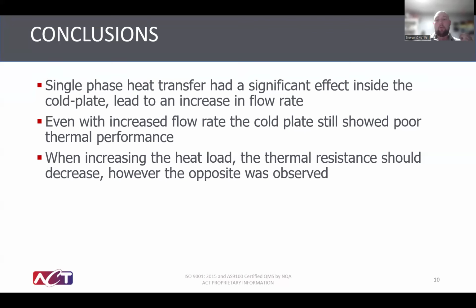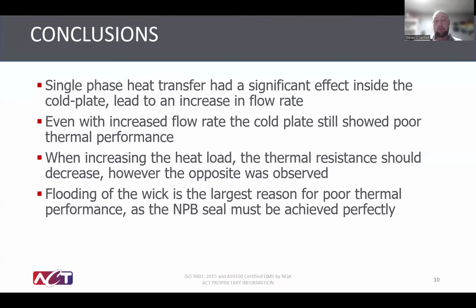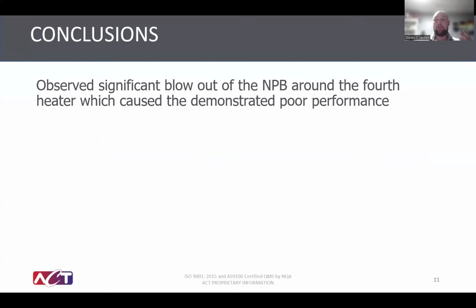One of the most major problems that can happen in a wick is flooding. That means the NPB seal is broken and refrigerant gets in, flooding the wick, or you dry it out if the seal breaks the wrong way. All of this hinges on the NPB seal being perfect, so we decided to take a closer look.